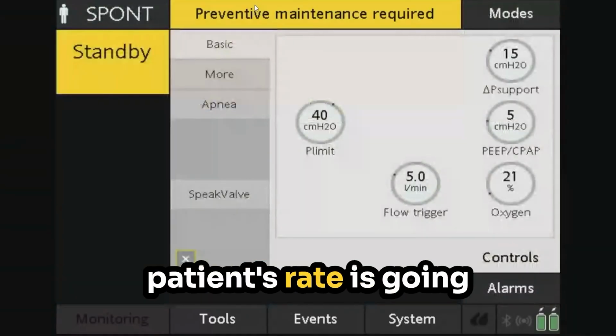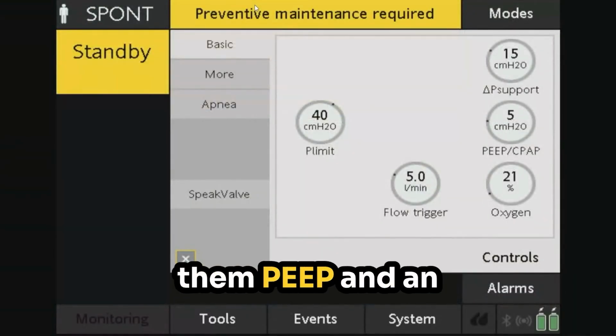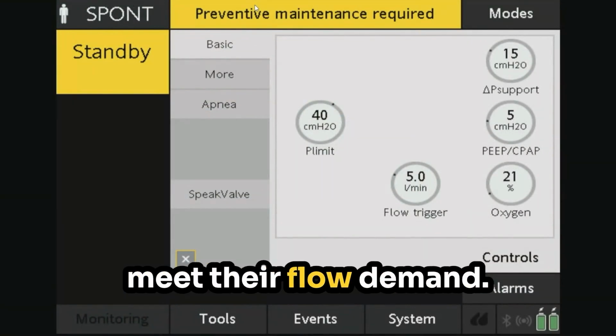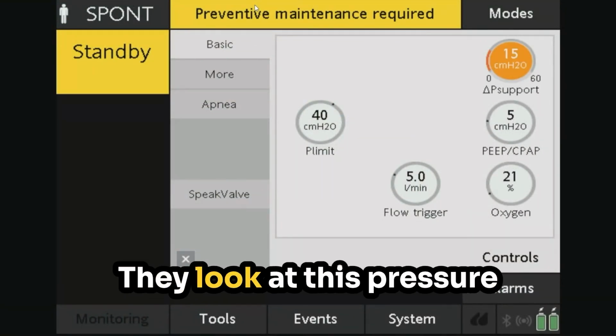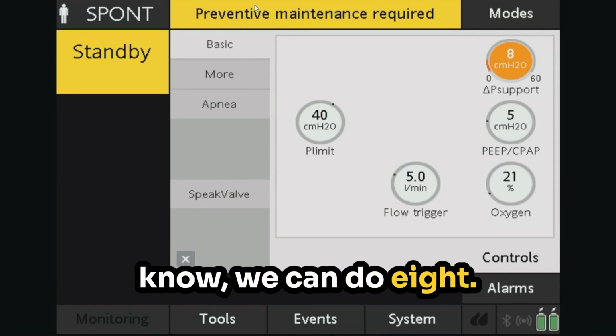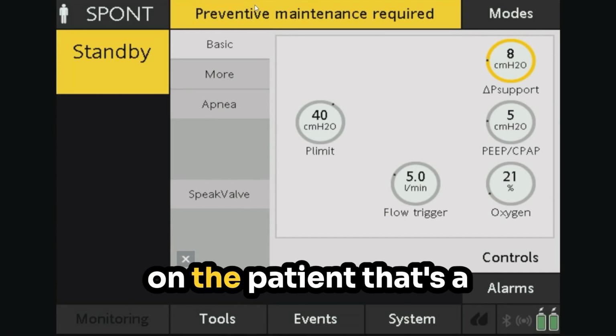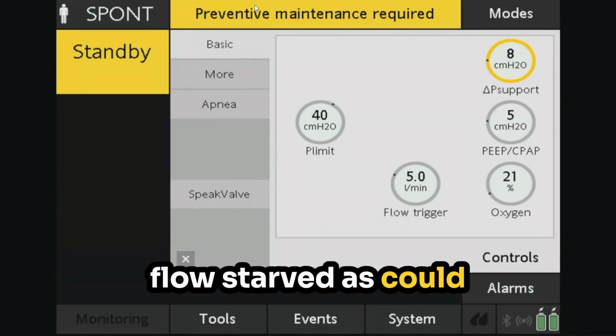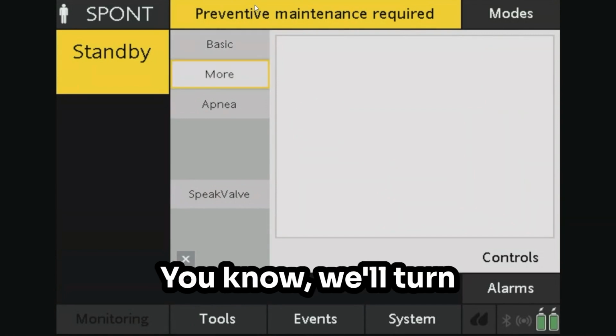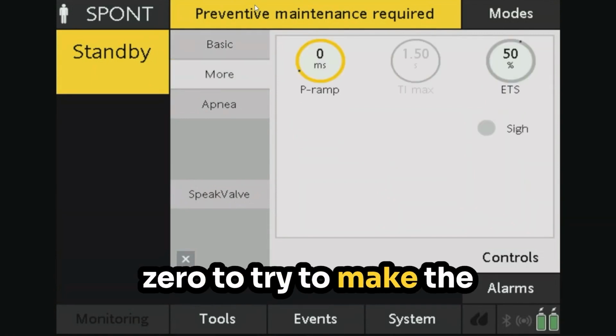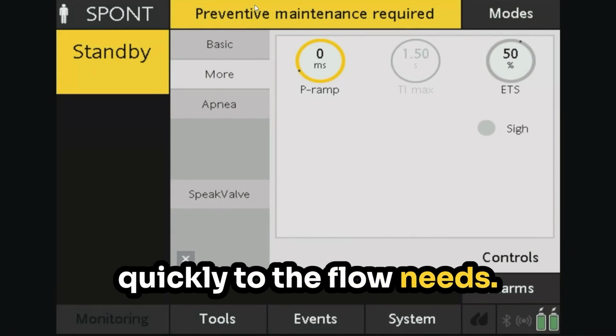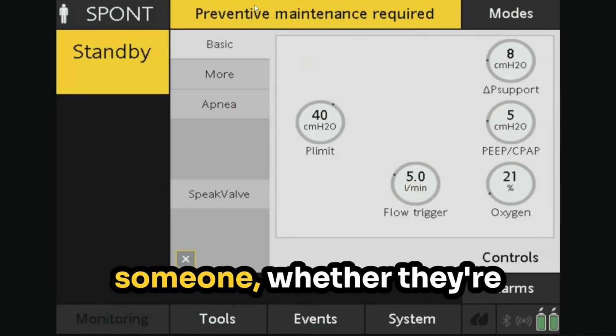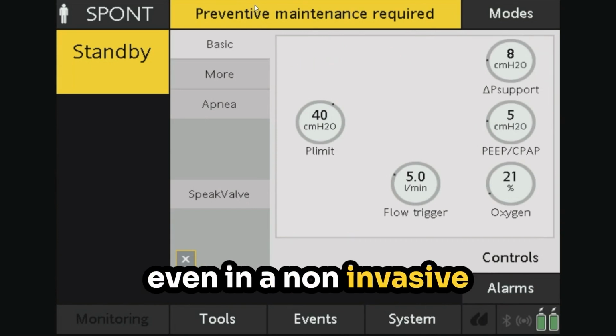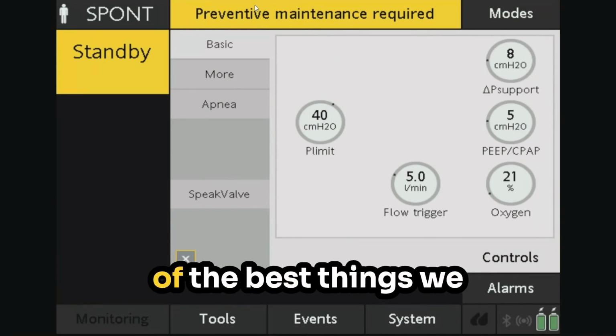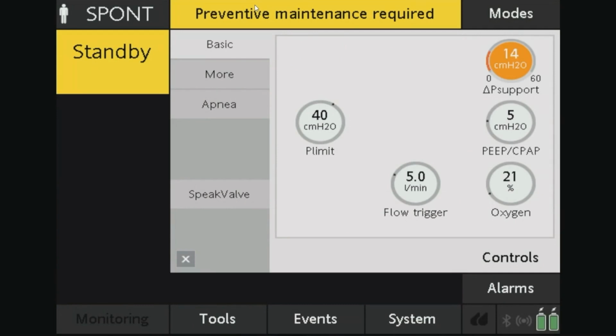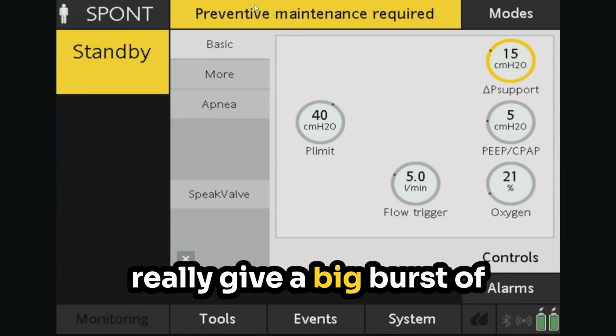So obviously the patient's rate is going to be what's driving it. We're going to provide them PEEP and enough inspiratory pressure to meet their flow demand. And here's kind of where people get in trouble. They look at this pressure support control. They think, we can do 8. And then you pop it on the patient that's a DKA and they're just flow starved as could be. And not incorrect, we'll turn the ramp down to 0 to try to make the controller respond quickly to the flow needs. But if we're trying to meet flow demands on someone, whether they're intubated DKA or even a non-invasive patient that's just air hungry as can be, one of the best things we can do is turn up the pressure support because that's going to really give a big burst of flow on the front side.